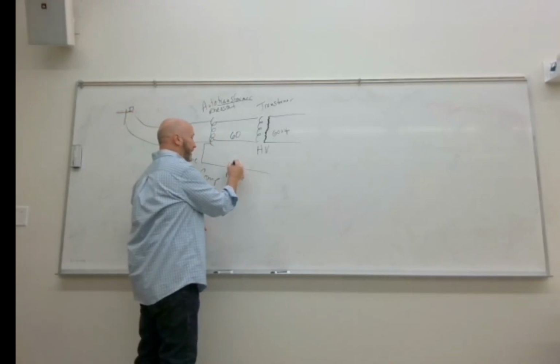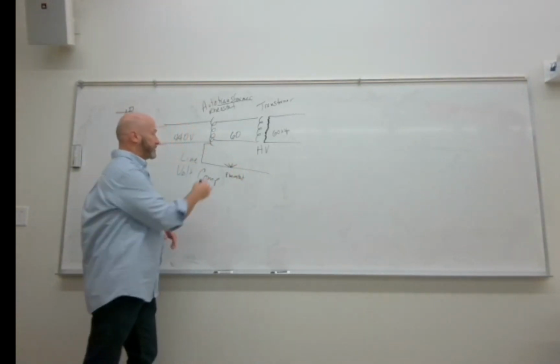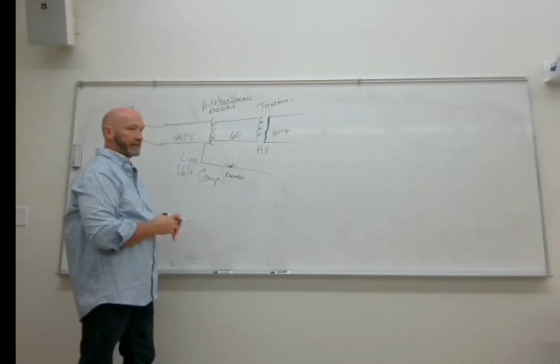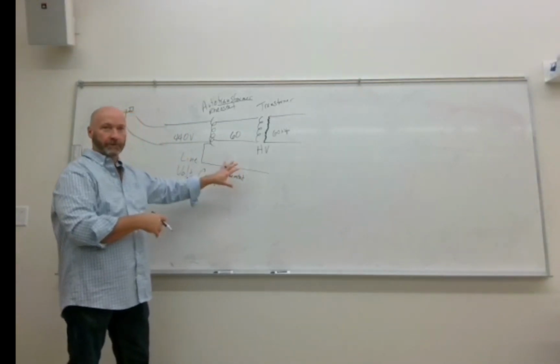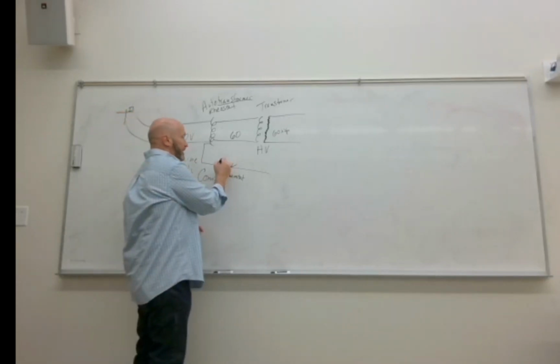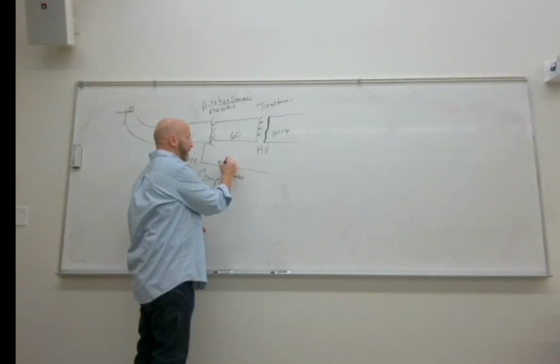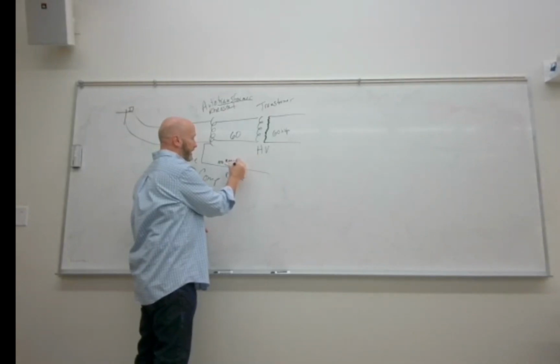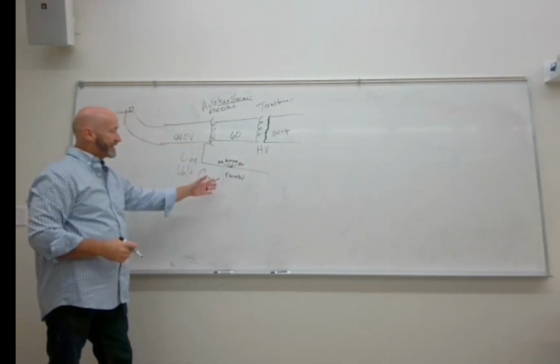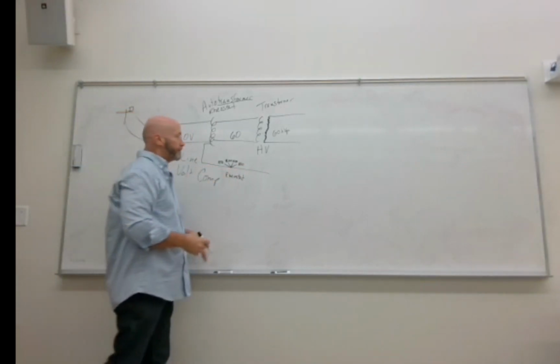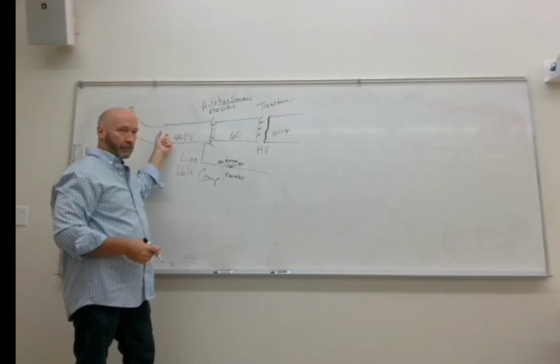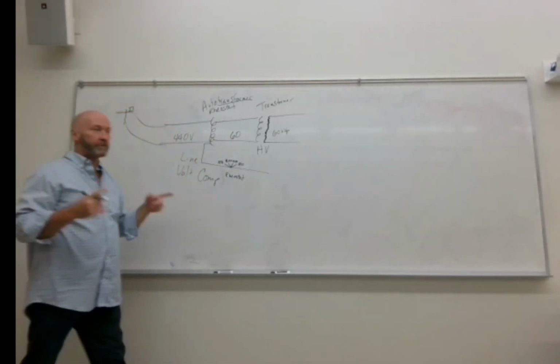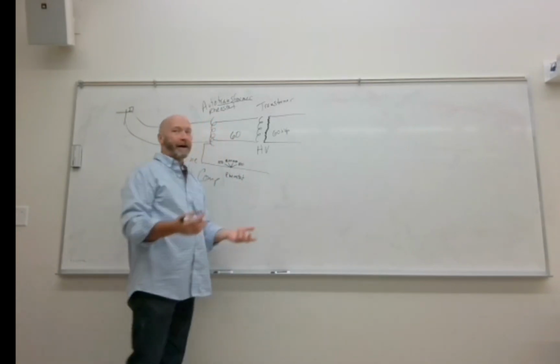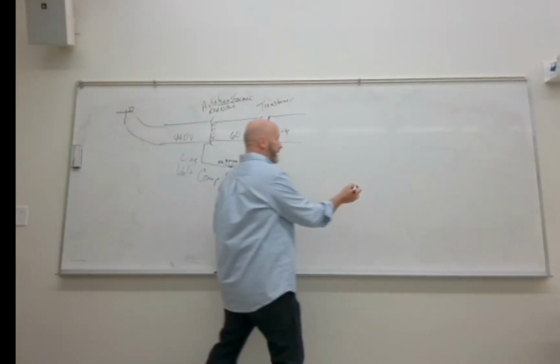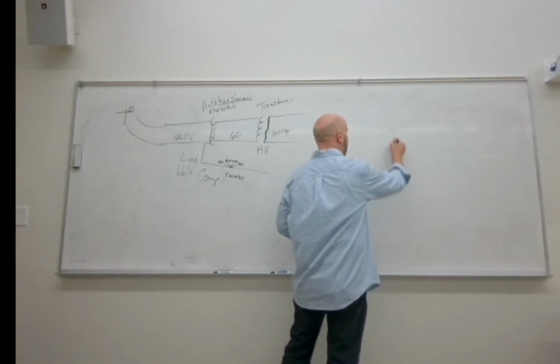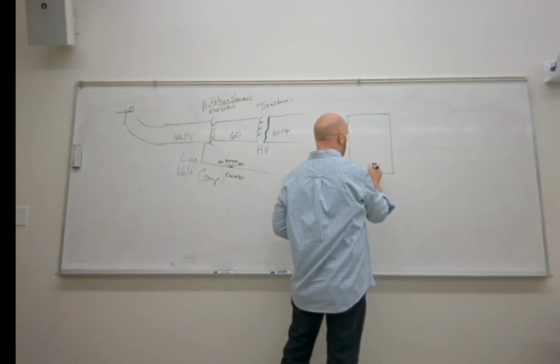With the mA, you've got select mA stations. And why they draw this one like this in the textbook, if you go further into the textbook, you'll see this drawing. But you've got specific mA stations, maybe 100, 200, 400, and 800 mA stations. So you've got set mA stations. So this is going to set your mA, but you're still working off of 440 volts. You don't want 440 volts. What you want is more like 25. And this is a reason, is because of what we're going to be talking about today, electrostatics and electrodynamics.